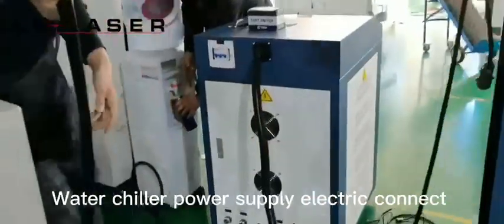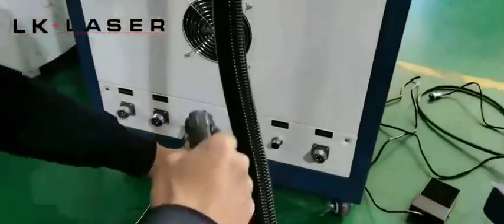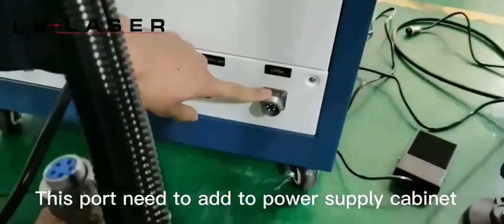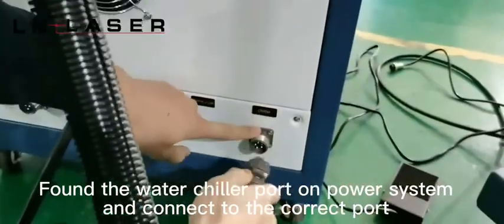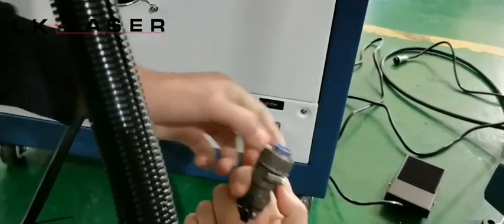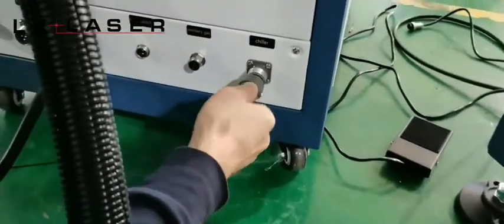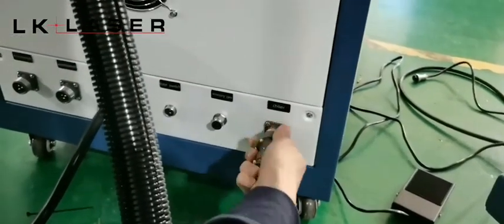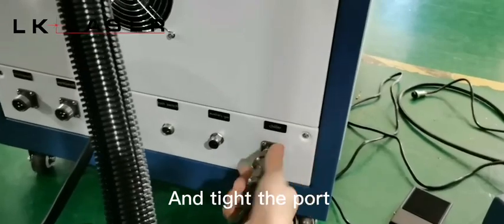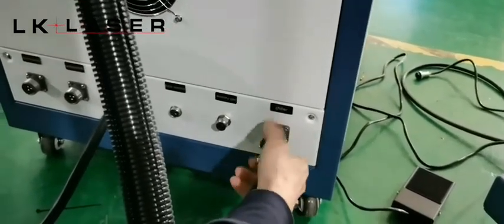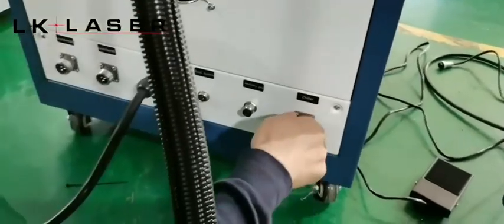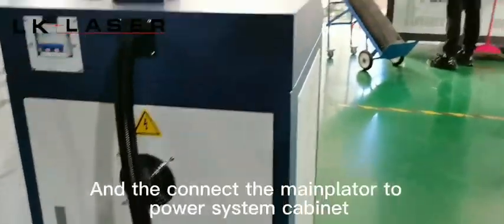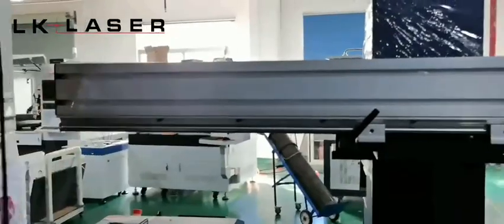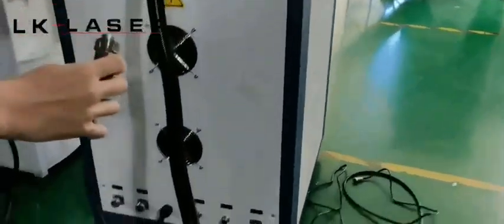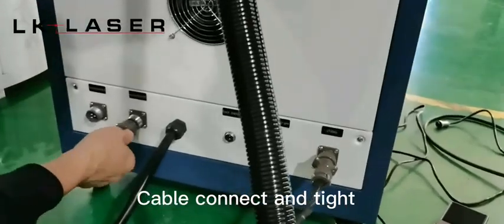Water chiller power supply electric connect. This port needs to be added to the power supply cabinet. Find the water chiller port on the power system and connect to the correct port, and tighten the port. And then connect the main plate to the power system cabinet. Cable connect and tighten.